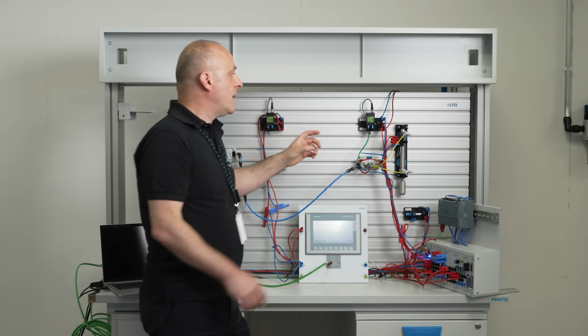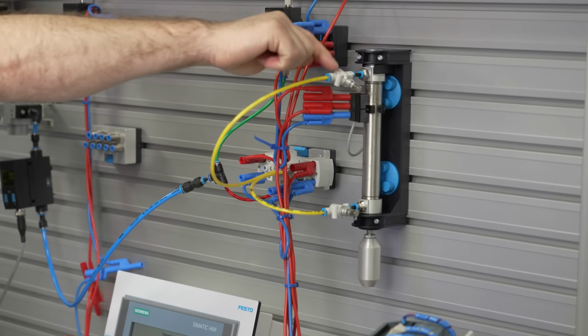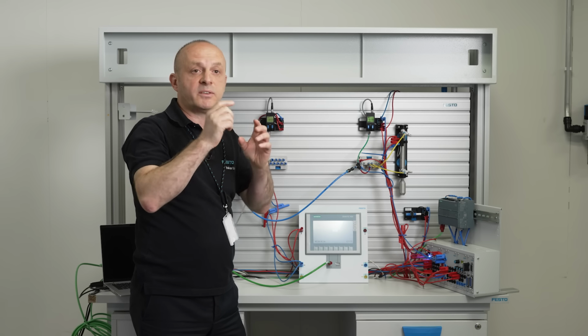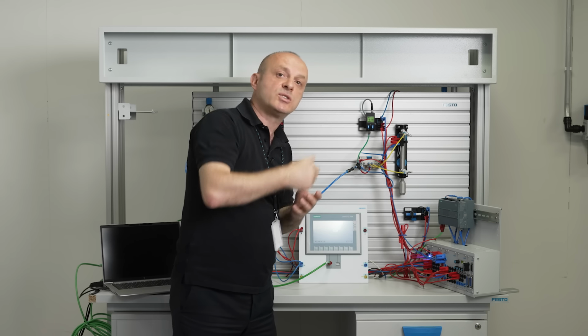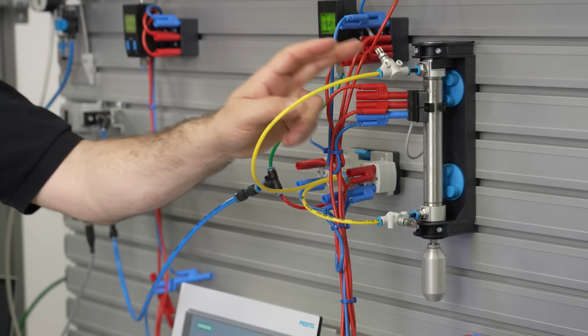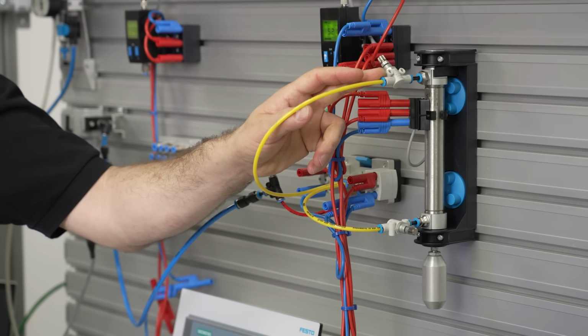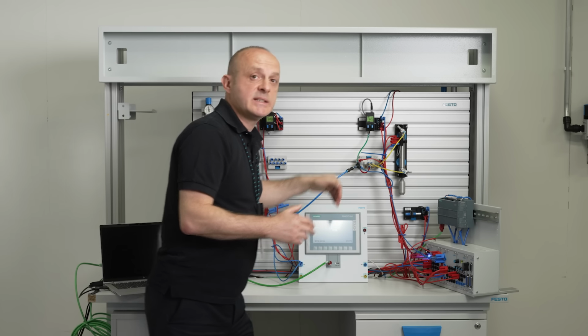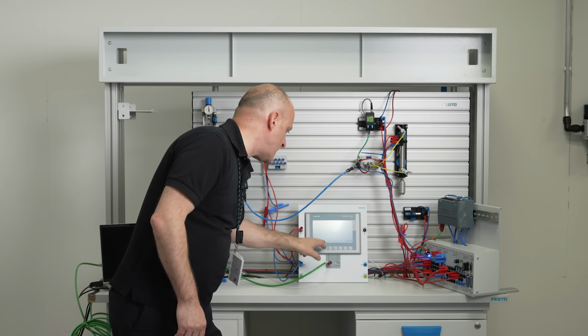Now what I will do, I will replace only this tube, the one-way flow control valve, the other way around. Basically, if we get confused, we can easily install them the wrong way around. Let's have a look at what effects you might have. This one-way flow control valve is installed the wrong way around, so we have made a mistake. We will advance the cylinder and have a look at the cycle time.